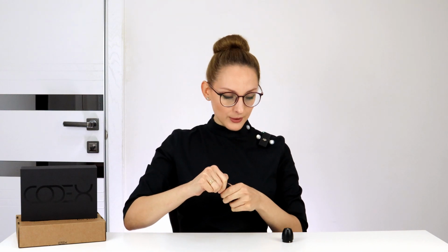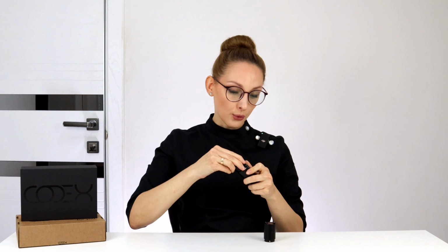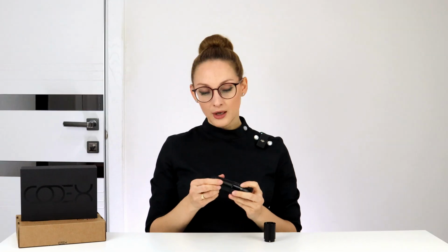The wireless battery provides about 4 hours of work. It depends on the operating voltage that you use while working. Changing the battery is effortless and smooth. Full battery charging takes 1.5 hours. Grip diameter is about 32 mm. We have to sterilize the grip. It can be disinfected and autoclaved. The instruction informs that a high temperature sterilizer box is prohibited. The high temperatures can cause deformation of the grip after sterilization.